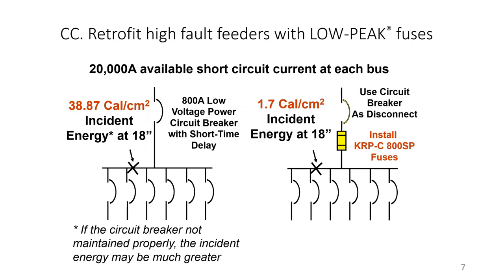And I have seen actual cases of equipment blowing up, causing fires and major damage, where the fuses just sat there, not clearing any fault. And it took a very long time by the time the fuses cleared the fault. And that was in situations where the fuses were installed in, for example, Midtown Manhattan, where the available fault current is very high, but the fact is that the fault did not occur at the service disconnect. The fault occurred upstairs on the 13th floor of the building or all the way on the other side of the building, and the available fault current that the fuse saw was relatively low, and it did not work in its current limiting region.